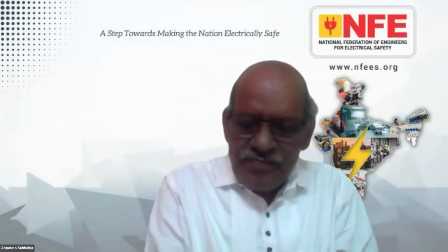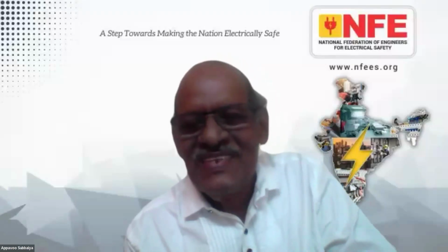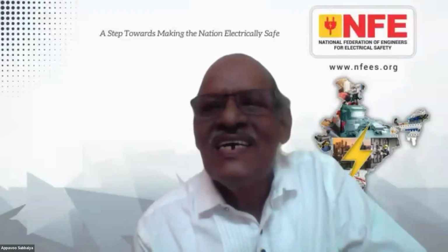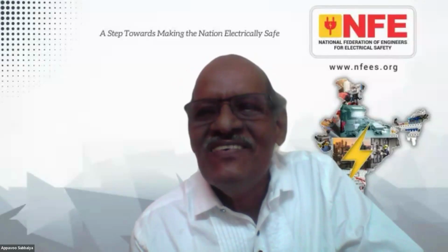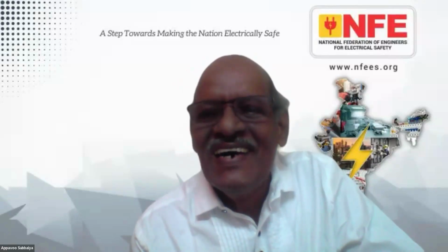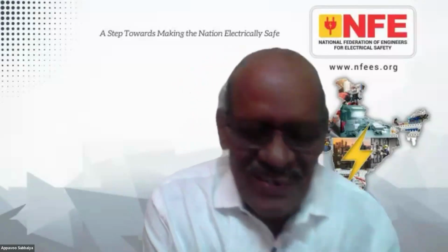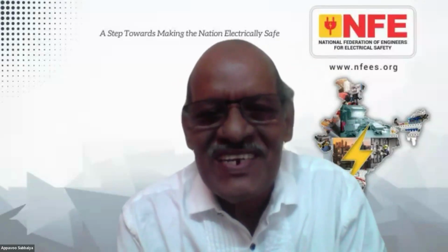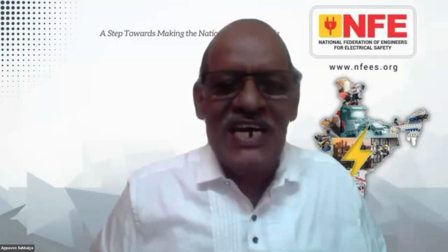As an additional safety measure, in case there is a leakage within the installation, this RCD provided at the origin of the installation will render the installation dead and ensure electrical safety. I think that is the intention behind this regulation. Right, yes, that's what I also feel, because our people always have some errors of omission and commission. There could be some missing, and the earth fault loop impedance is a new concept.